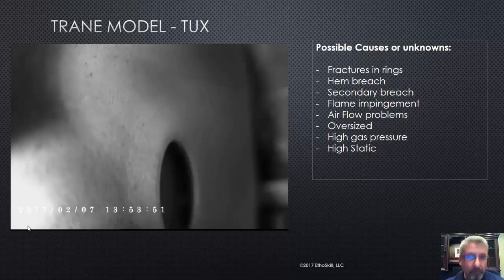So, what do we learn from this? A whole bunch. Here's the deal. Service techs. When you're out on maintenance calls, check everything. Check your static duct pressures. Check your temperature rise. Check your heat exchanger. Check your gas pressure. That's functional stuff. Now then you have to do your safety, your combustion analysis. Check for gas leaks, all that business, all right?